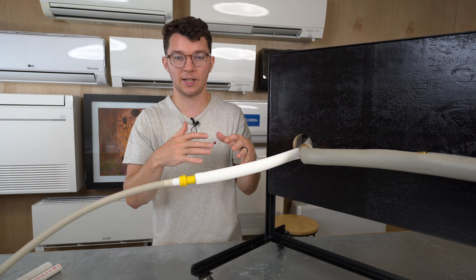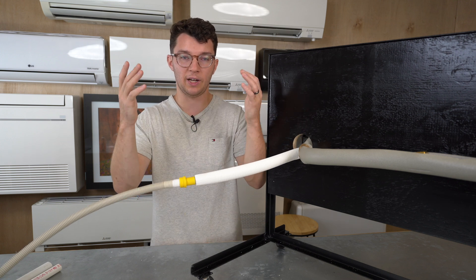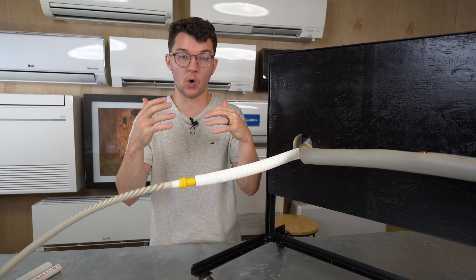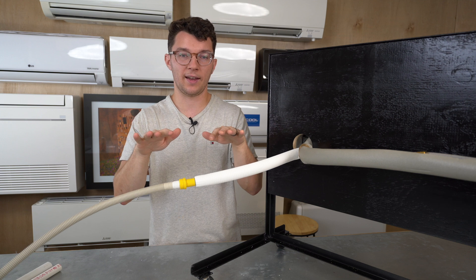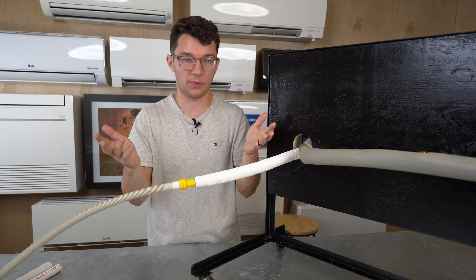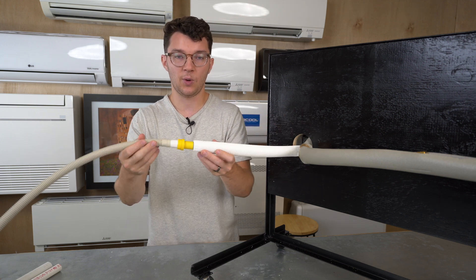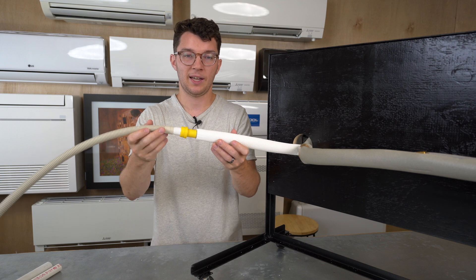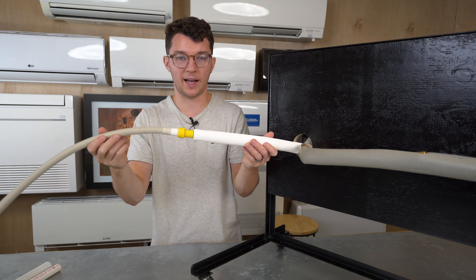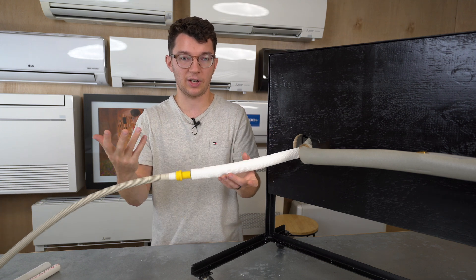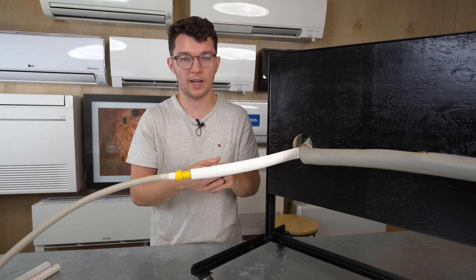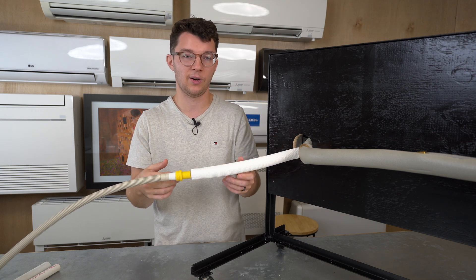When your system is draining, it's pulling out any dust or anything from the coil and draining it away with regular condensate. So if you have gunk that's building up and you have a barely sloped line, that gunk is going to build up and you're going to have a clog. It's going to cause your indoor unit to shut off with an error code.